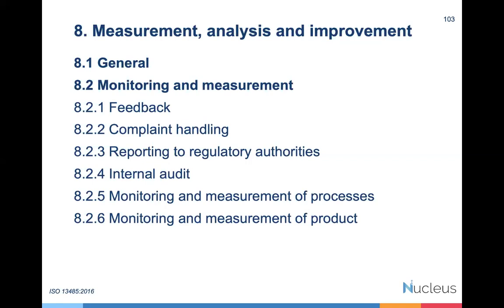The complaint handling mechanism covers how you deal with issues after manufacturing a medical device and delivering it to your customer. Technically it goes to dealers or distributors, then reaches hospitals, then reaches technicians and biomedical engineers. What type of mechanism do we need to handle complaints from those people? Reporting to regulatory authorities is required when any non-conformities are found during monitoring and measurement. Advisory notices fall under clause 8.2.3.